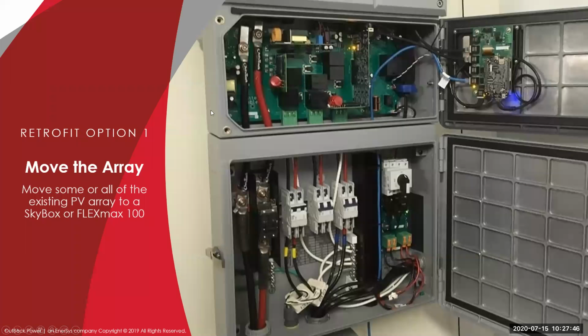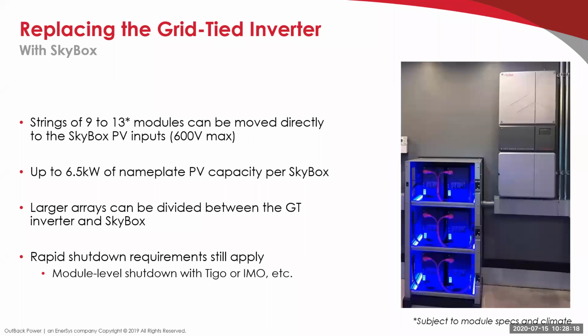Let's go back to this previous stage. So we have two inputs here. They're actually in parallel, so you could just put a single string here. You can have up to 6,500 watts connected. Now Skybox is only going to convert 5,000 of that, but you can have 6,500 watts, because most arrays are only going to run about 75% efficiency max anyway. You could hook up two strings, but they would be in parallel on a single MPPT. Okay, so this could be a good way to go.